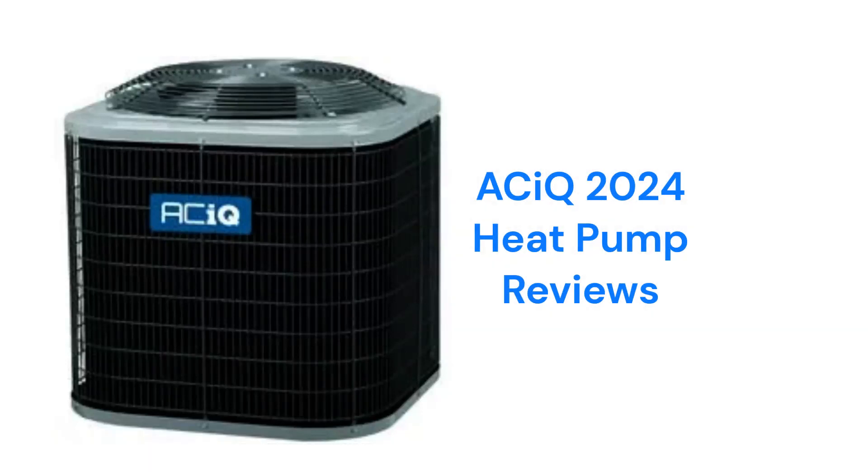This brand is made in Mexico by Carrier and the heat pumps can be purchased online through HVAC Direct. The units only use a wire mesh protection for the condenser coil, which doesn't do much to protect the coil from damage due to flying debris from a lawnmower or hail. The guarantee on the brand is not as good as some other brands. The units use R410A refrigerant, which is not as earth-friendly as brands that use R32.